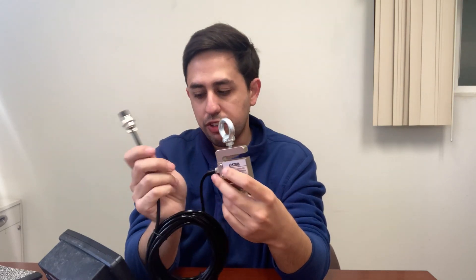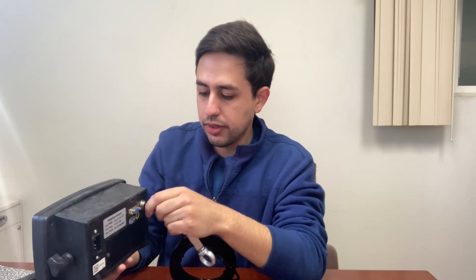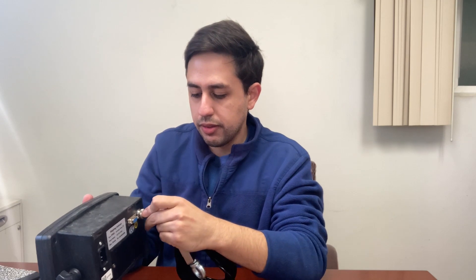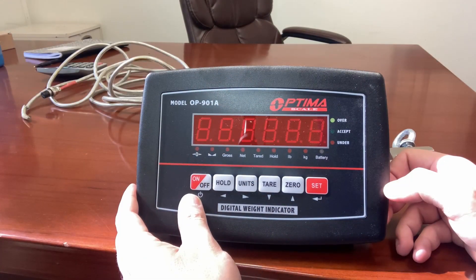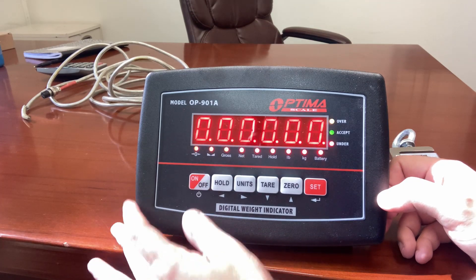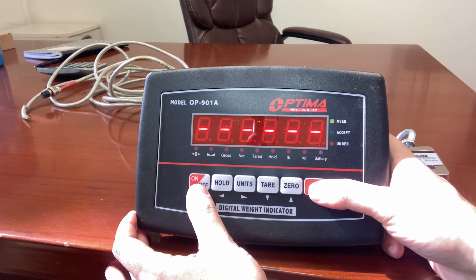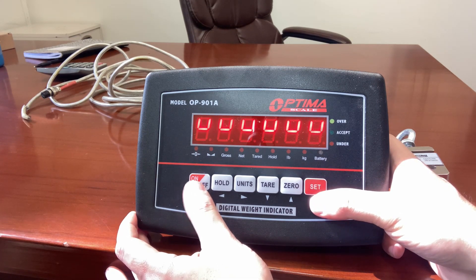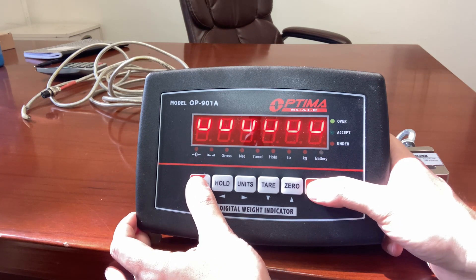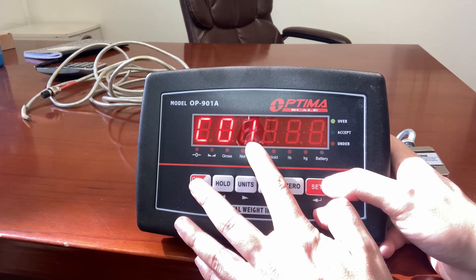Make sure it's connected to the back of your indicator. Next, you're going to turn on your indicator — press the on-off button. To enter calibration, press the on-off and set button at the same time for three seconds. C01 should appear.